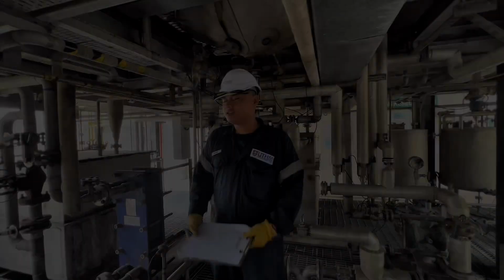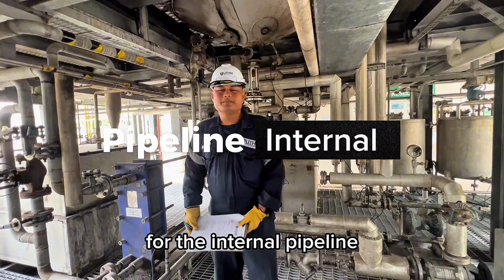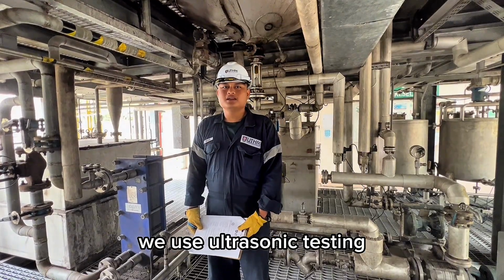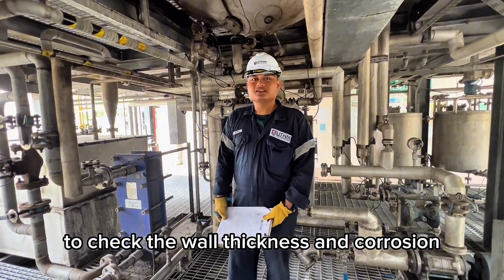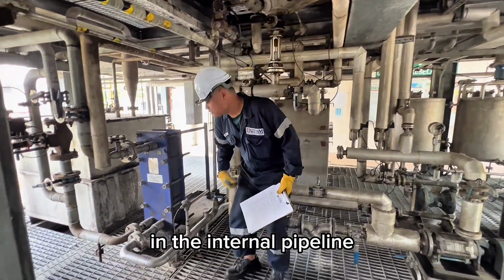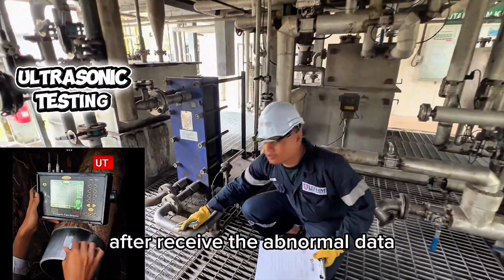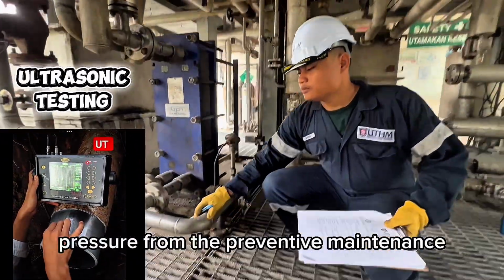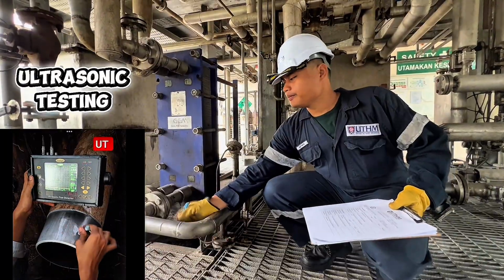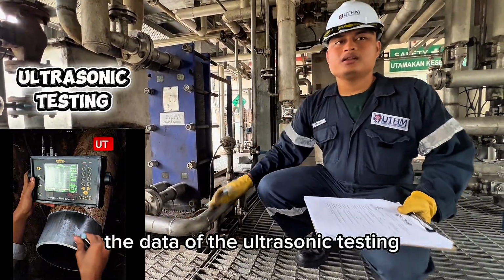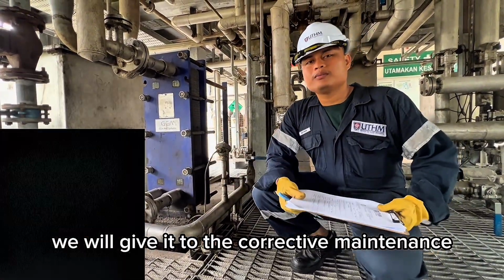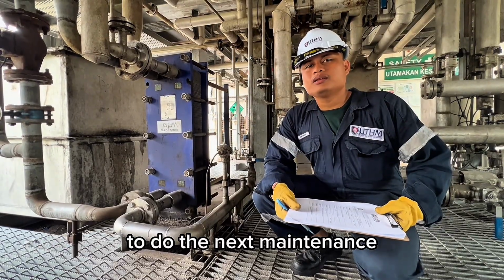For the internal pipeline, we use ultrasonic testing to check the wall thickness and corrosion in the internal pipeline after receiving the abnormal pressure data from the preventive maintenance. The data of the ultrasonic testing, we will give to the corrective maintenance to do the next maintenance.